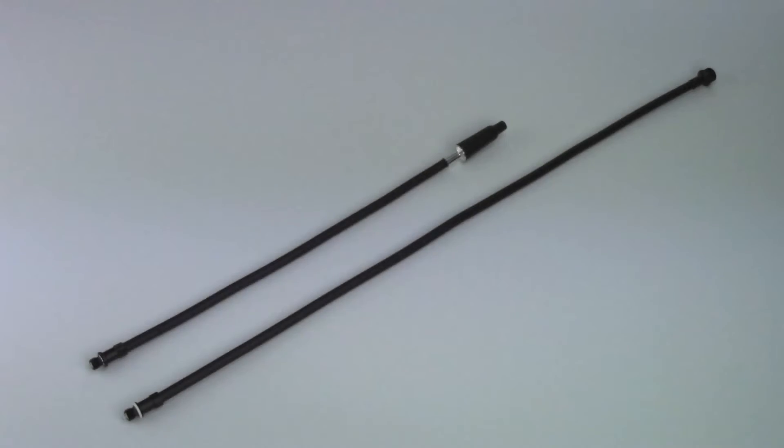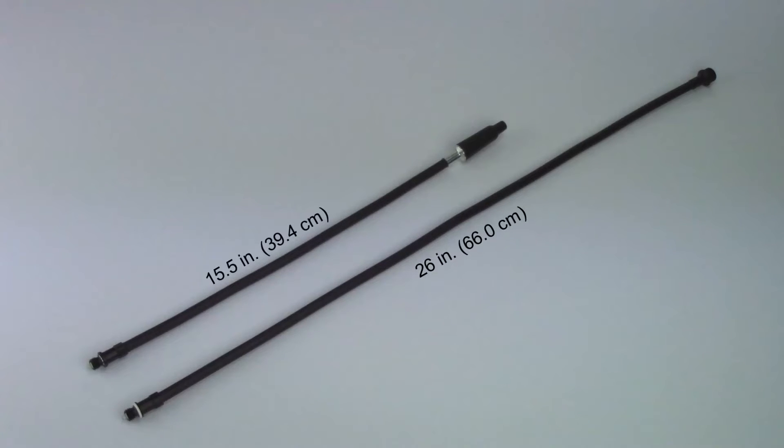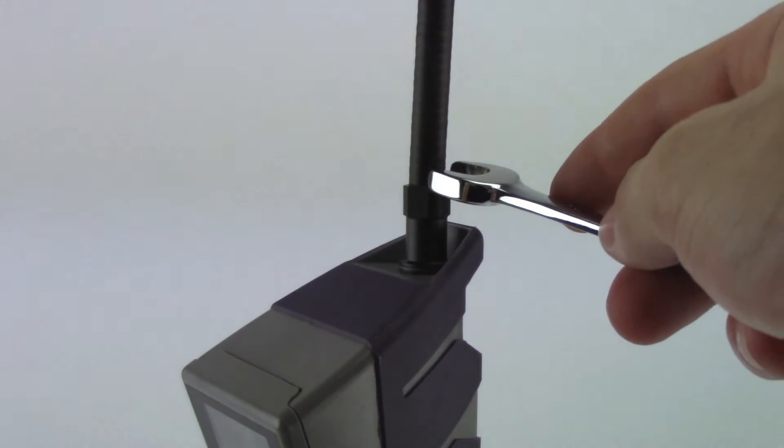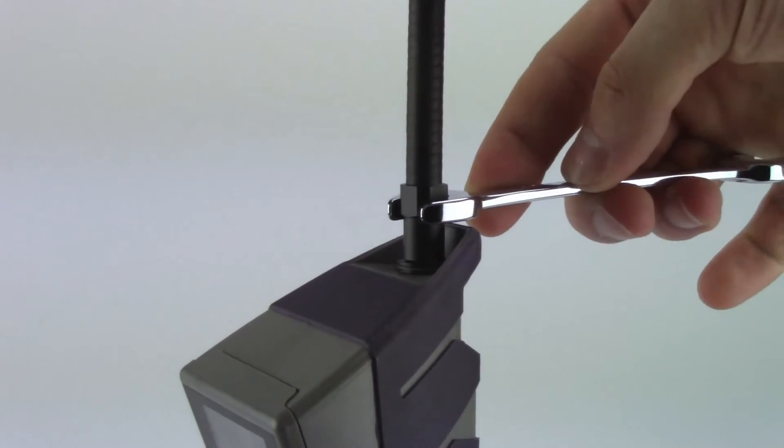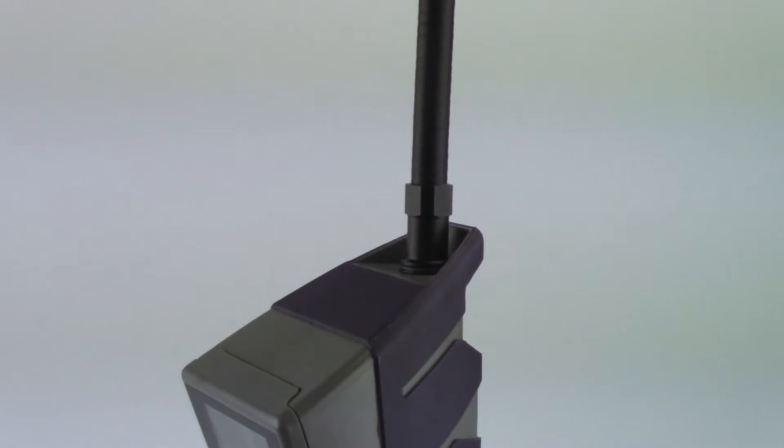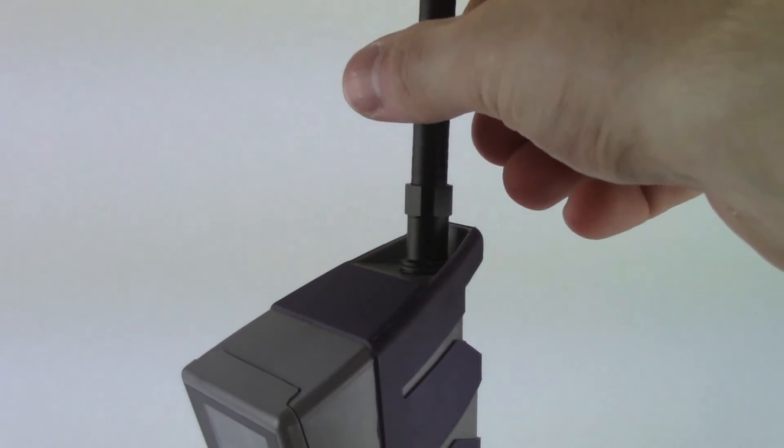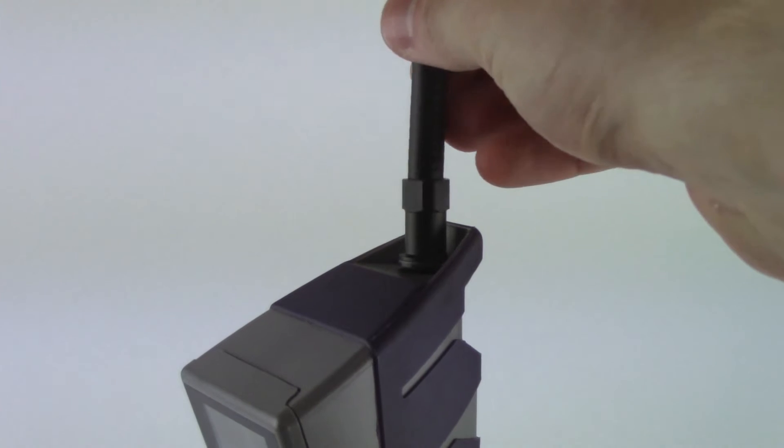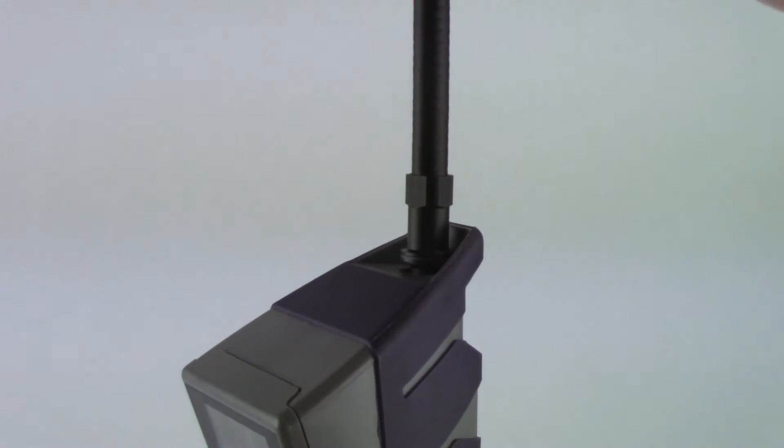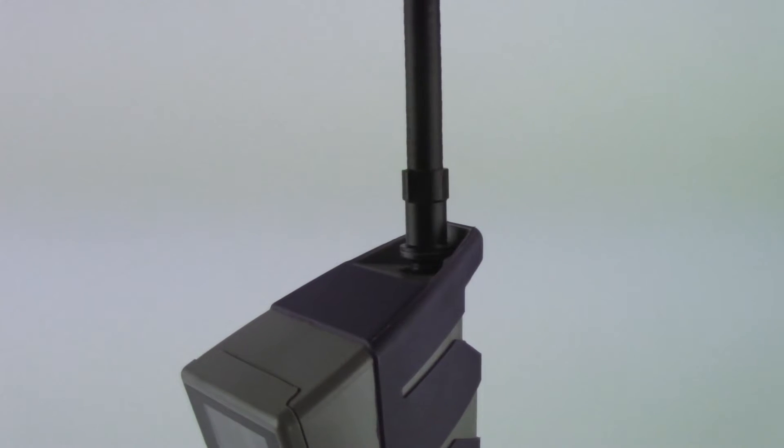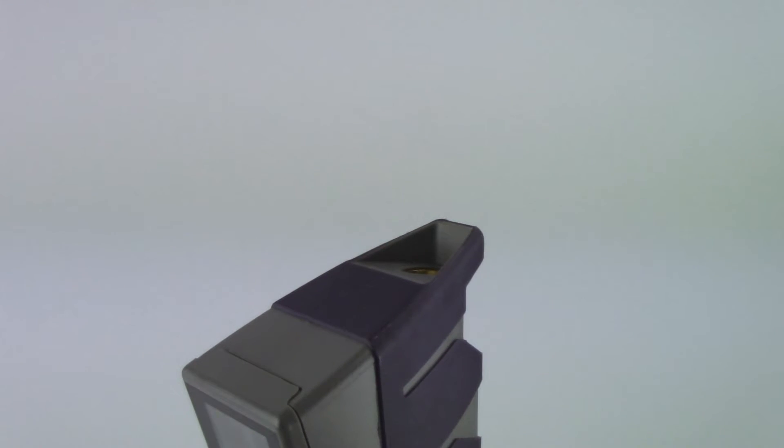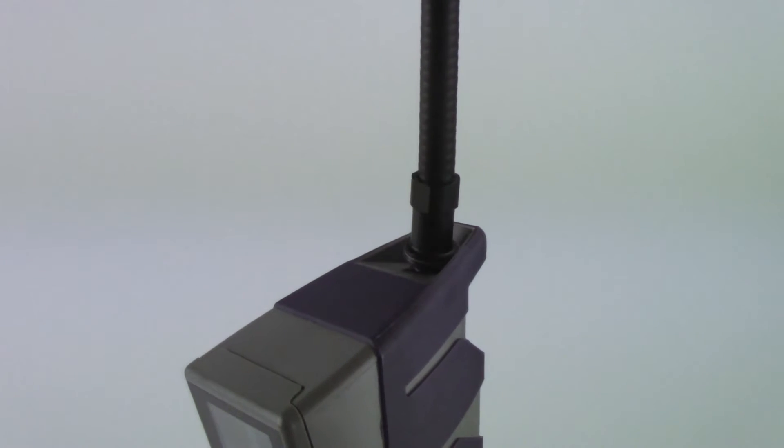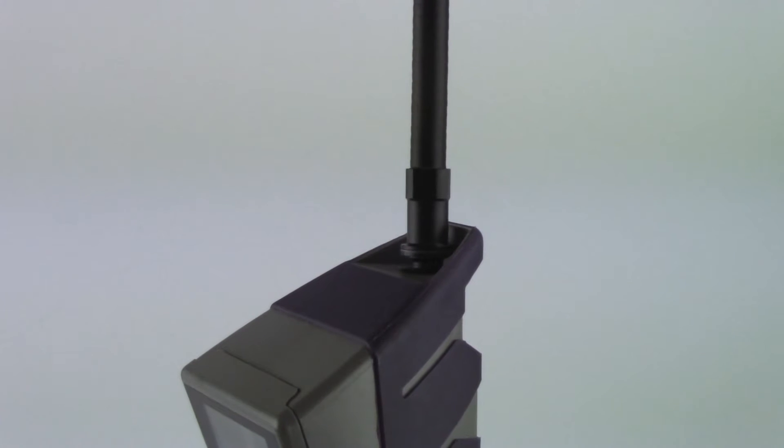The extra-long probe can be used for those hard-to-reach places. To install the extra-long probe, unscrew the original probe using a 10mm wrench. Screw the extra-long probe on and torque to about 35 inch-pounds or 4 Nm of torque.